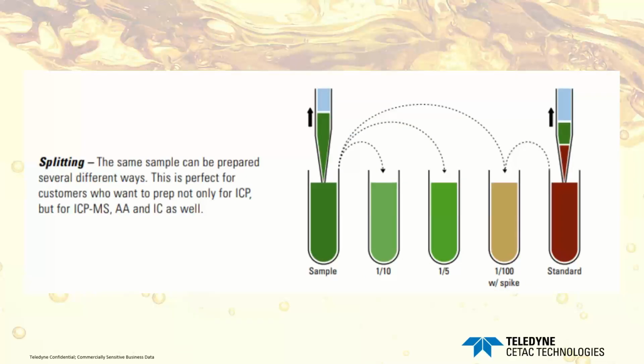Right. And then we also have sample splitting, which can be very useful for an in-service lab. If your current coolant workflow requires different dilution ratios for different tests using the same sample, you can let the SimPrep handle that for you. Here we're showing where we're taking one sample and making a 1 to 10, a 1 to 5, a 1 to 100 with a spike. All for different tests, whatever you need, the SimPrep can prepare that for you.